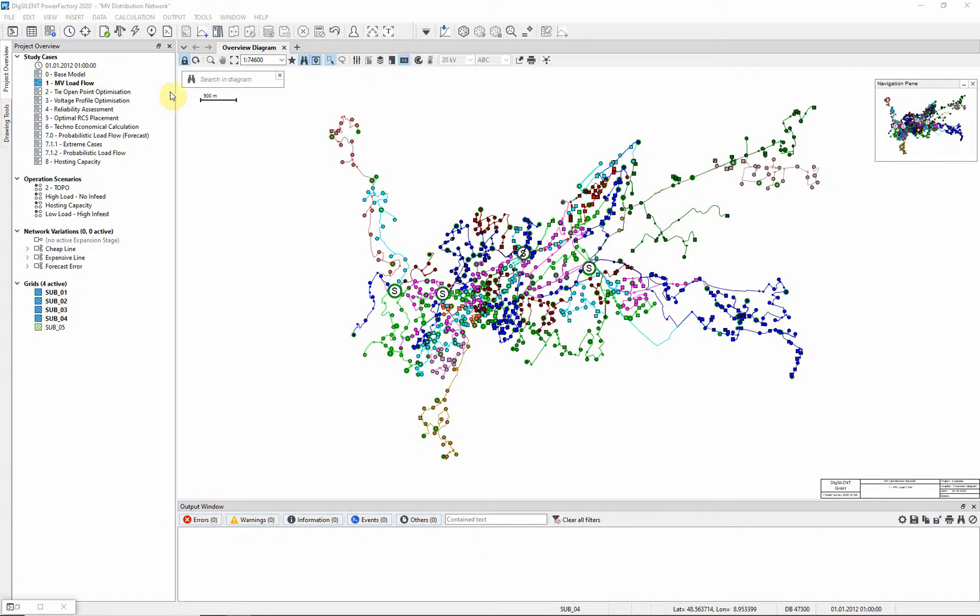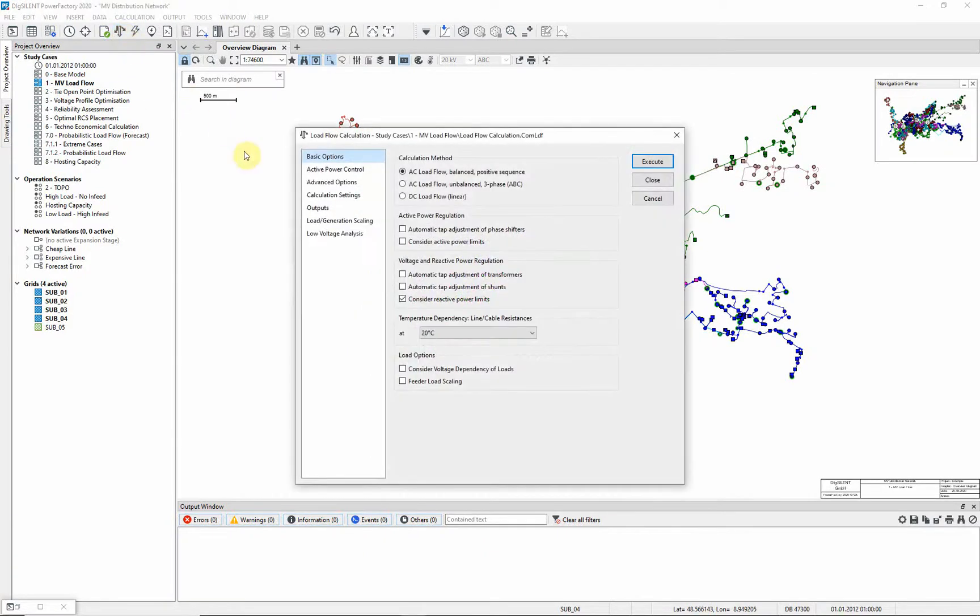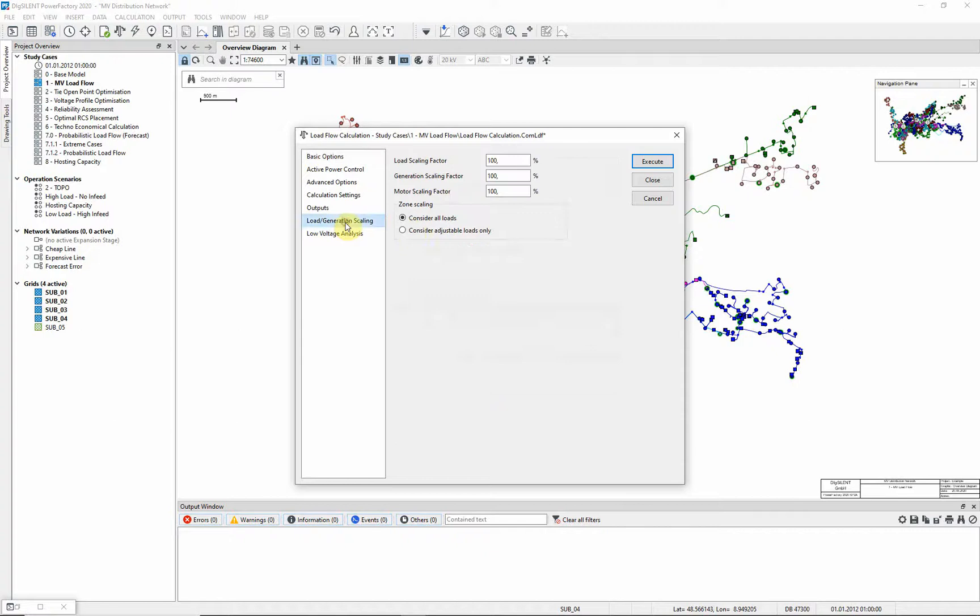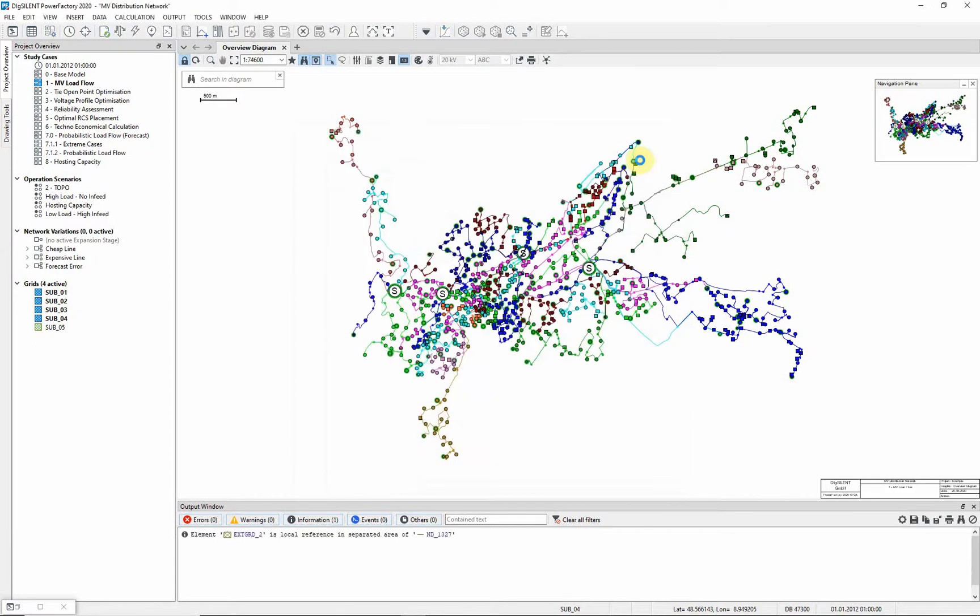To run the load flow, select the load flow icon. Ensure that the option automatic tap adjustment of transformers is selected. On the load and generation scaling page, ensure that the load and generation scaling factors are both set to 100%. Execute the load flow.